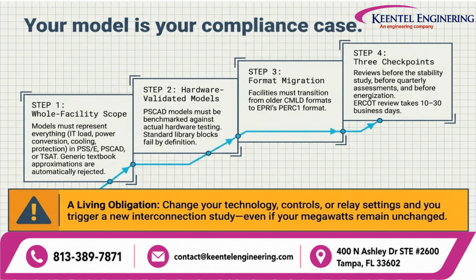The presentation specifically identifies modeling platforms such as PSSE, PSCAD, and TSAT. The second checkpoint is hardware-validated models. For PSCAD models, the model should be benchmarked against actual hardware testing. Generic textbook approximations are not sufficient when the objective is to demonstrate how the real equipment will behave. The third checkpoint is format migration.